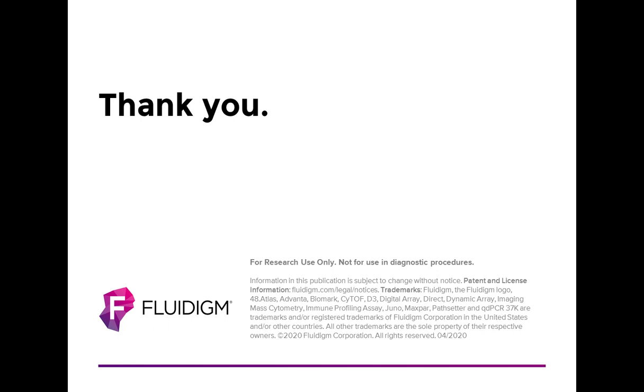Our workflows vary depending on the IFC itself and the protocol chosen. We have specific scripts that support relatively short turnaround times of just a couple of hours, and others that go longer, but all are less than four hours in total. One of the things we promote about our technology is the capacity of throughput. We can go up to 192 samples at a time, and with a couple-hour run time you're able to get thousands of samples in a day. This is not a point-of-care test — it's not a five-minute test like the Abbott test developed with ALEER technology — but it is high throughput and high capacity.